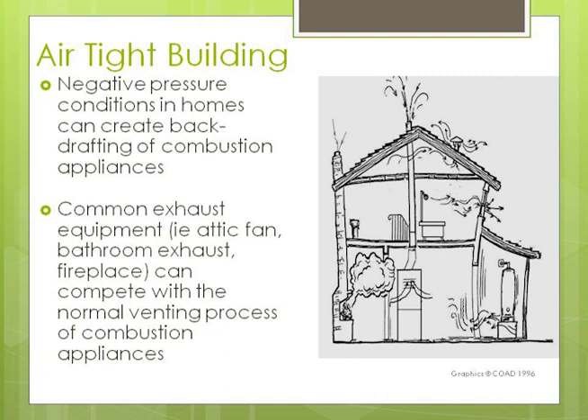As we get buildings more and more airtight, things like gas leaks and carbon monoxide become more of a problem than they would have been if the home was still leaky. If we're telling people to caulk and get new windows and do things to make their house tighter, but they've got gas leaks and problems that will be accentuated by following our advice, that's a problem. That's why we need to be careful not to make the problem worse by making the house tighter.